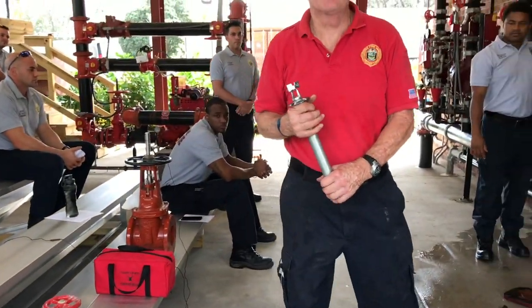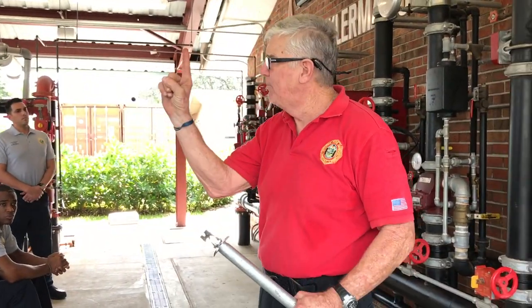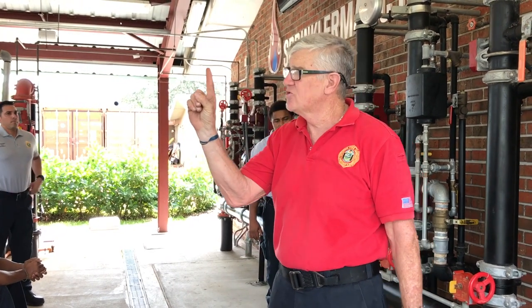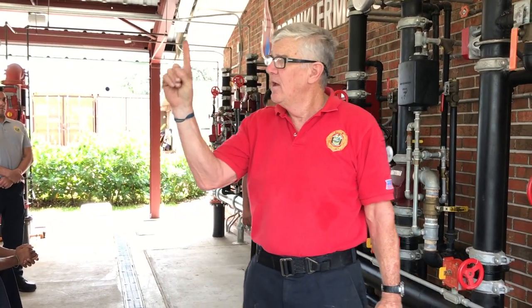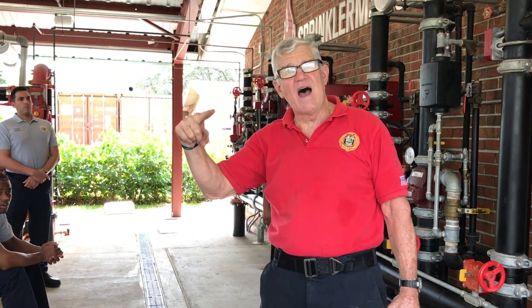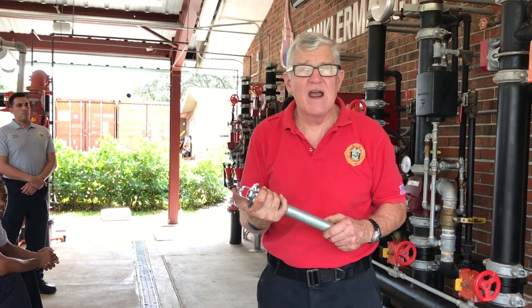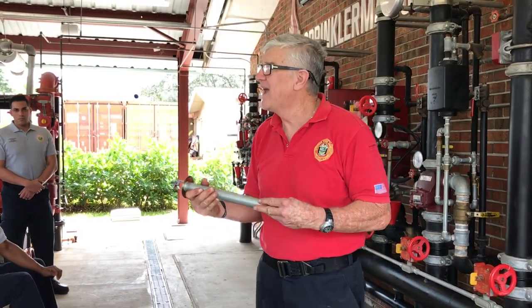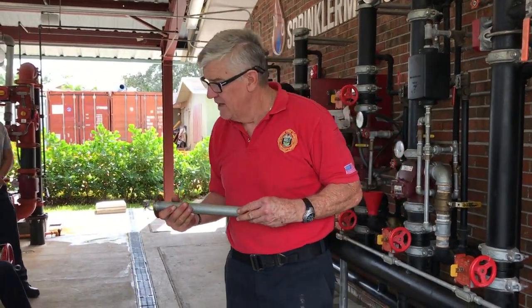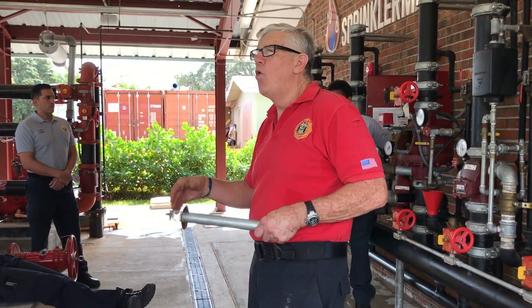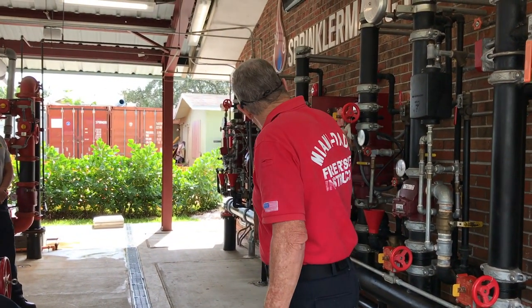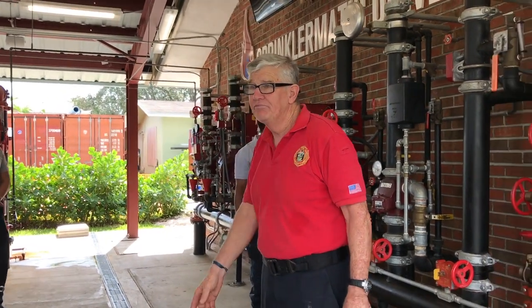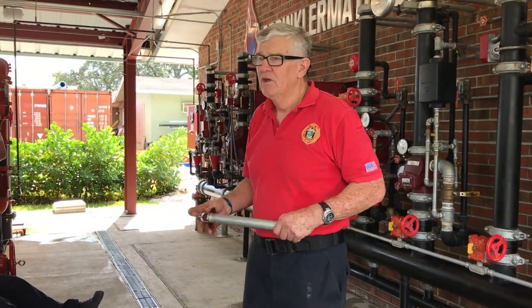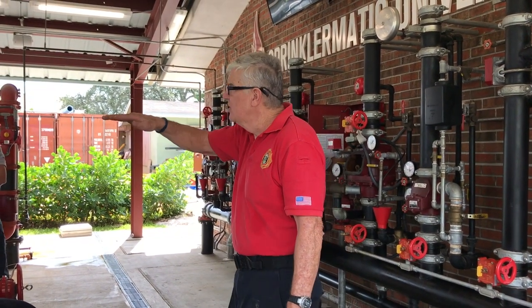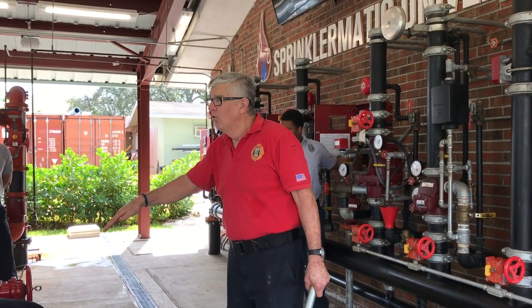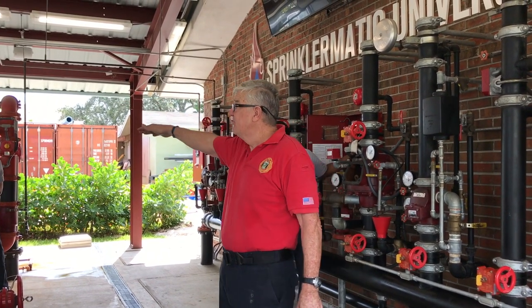In a dry pipe sprinkler system, you typically will find upright heads. And of course, as firefighters, you know, there's three types of sprinkler heads. Upright, pendant, sidewall. This happens to be a sidewall head. This is called a dry pendant head. Consider this. You don't want to bear the expense of a dry pipe valve. What if we did this? What if we had walk-in chillers, walk-in coolers, walk-in freezers, where above them is ambient temperature?